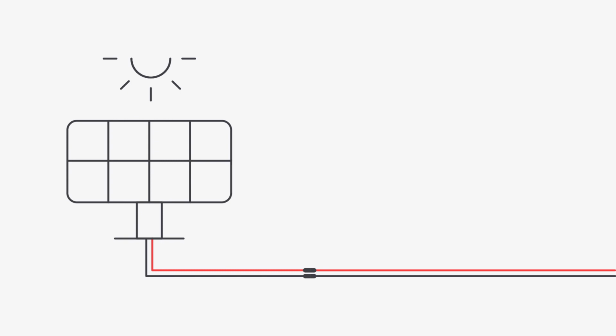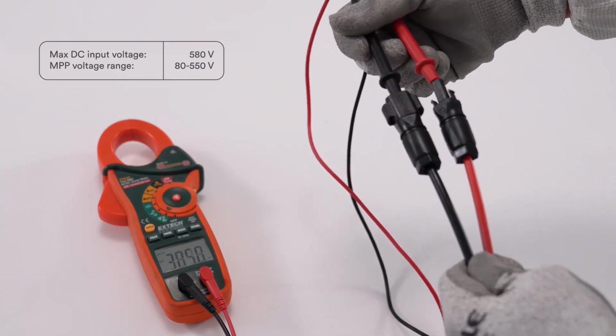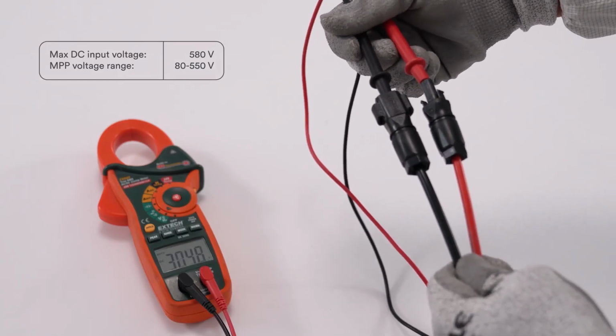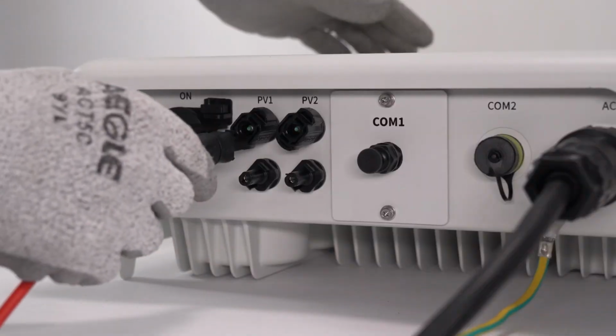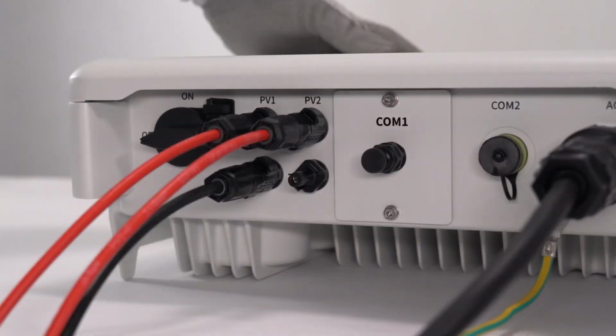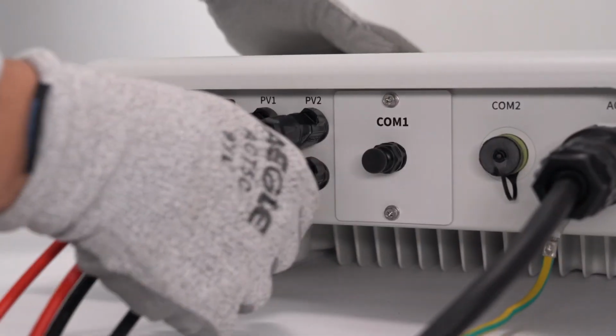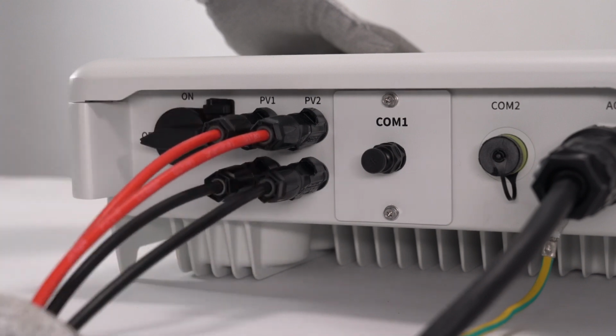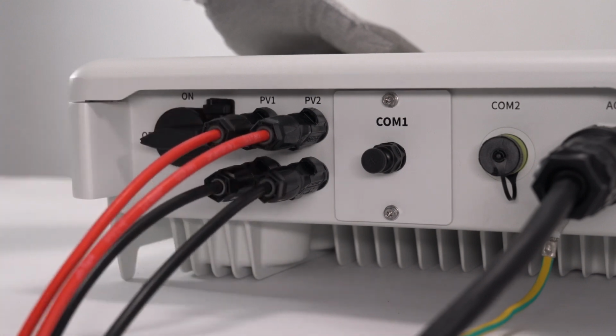Connecting the PV array. Check whether the DC connector has the correct polarity. Ensure that the open circuit voltage of the PV array does not exceed the maximum DC input voltage of the inverter. Connect the assembled DC connectors to the inverter until they audibly snap into place. Ensure that all DC connectors are securely in place. Seal the unused DC inputs with sealing plugs so that moisture and dust cannot penetrate the inverter.